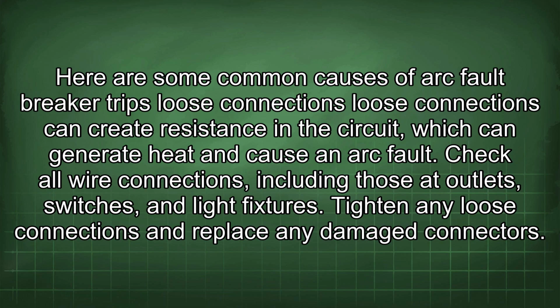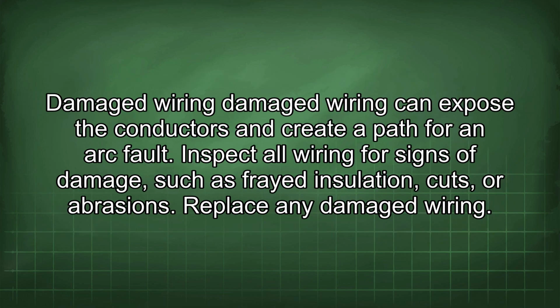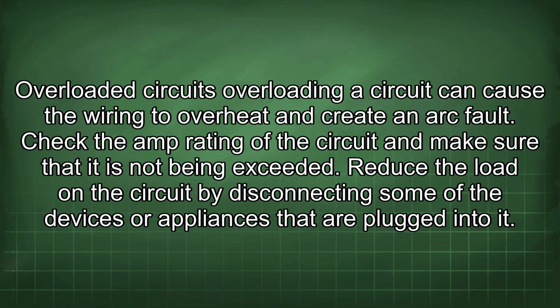Loose connections. Loose connections can create resistance in the circuit, which can generate heat and cause an arc fault. Check all wire connections, including those at outlets, switches, and light fixtures. Tighten any loose connections and replace any damaged connectors. Damaged wiring. Damaged wiring can expose the conductors and create a path for an arc fault. Inspect all wiring for signs of damage, such as frayed insulation, cuts, or abrasions. Replace any damaged wiring.